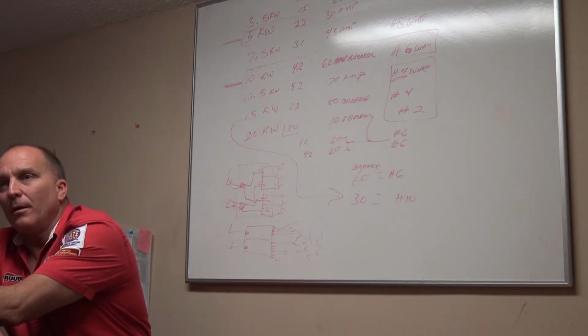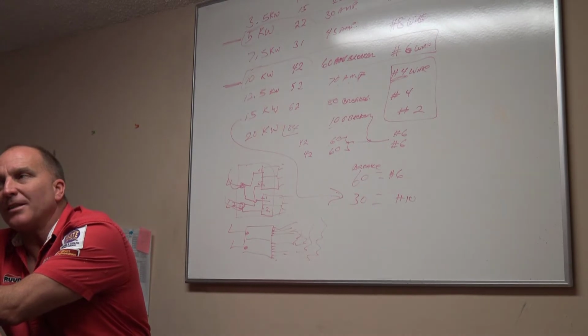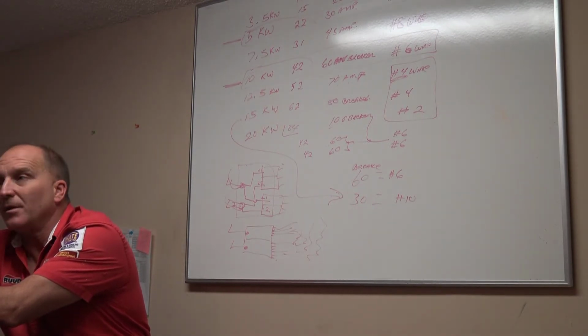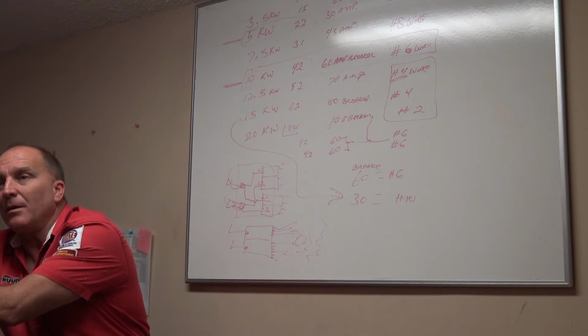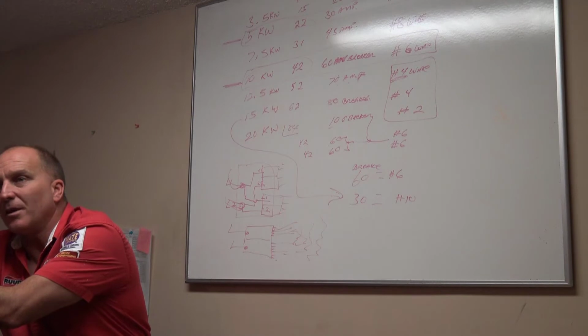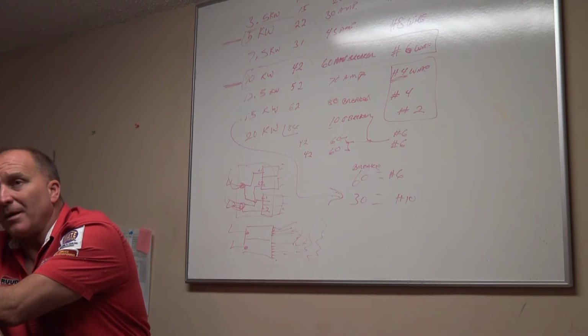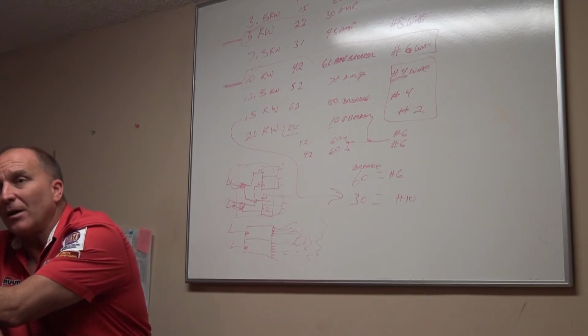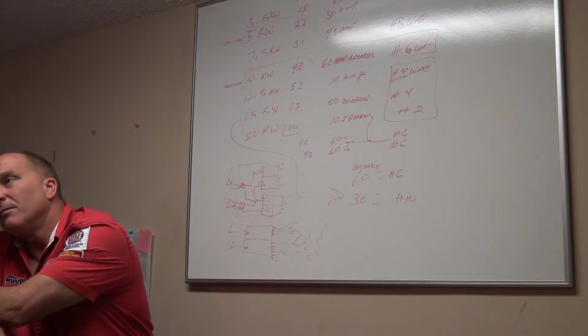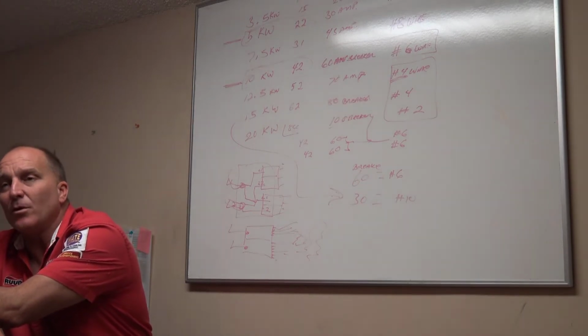So therefore, them running that blower speed on high speed with 15 kW is going to get your proper delta T. But running high speed here in the south, when you only need 10 kW and running it on high speed, your delta T is not proper. Does that make sense? Yeah. Higher the blower speed, the lower the delta T. Slow your blower speed down, the higher the delta T. Remember, when you check your heating system, I want you to check your delta T to see what your heating system should be between 35 basically and 55 is where your delta T should be.